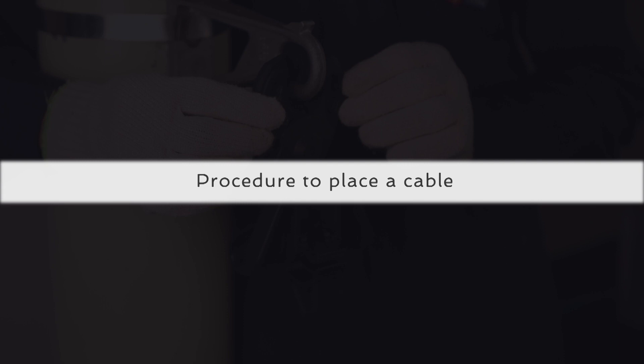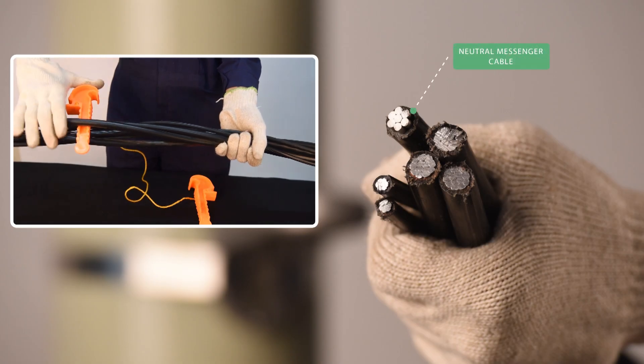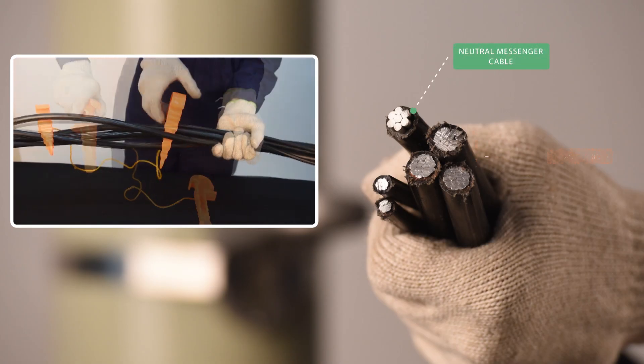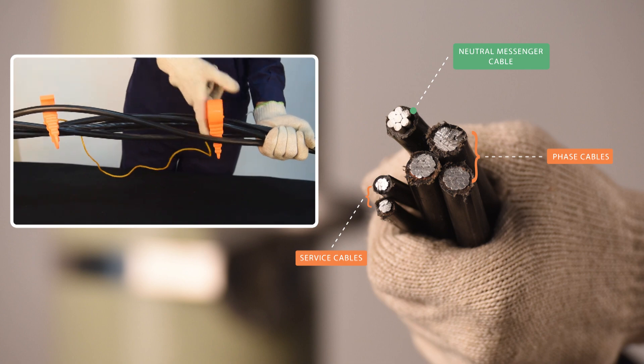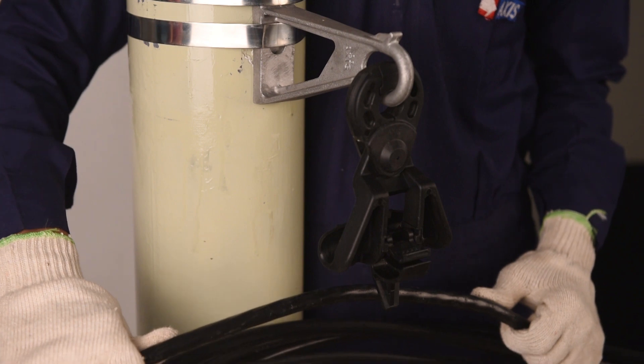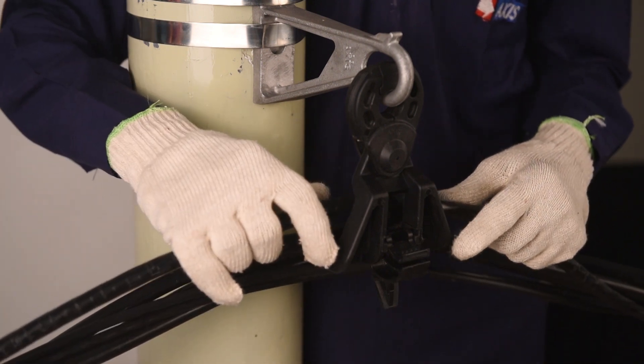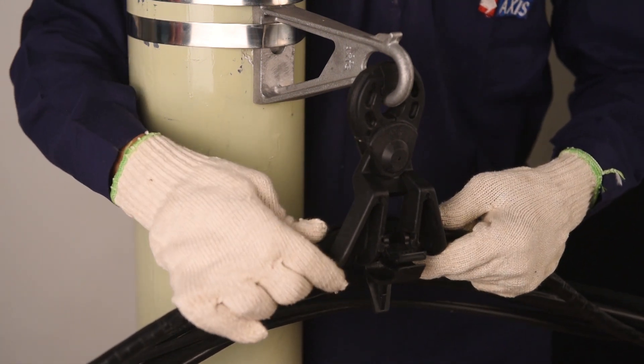Let us now understand the procedure to place a cable. Identify the neutral messenger cable and separate it from the other phase cables using a phase separator. Place the neutral messenger cable in the holding area of the clamp body.